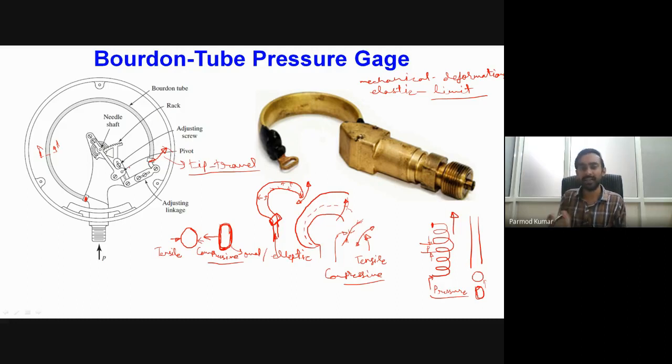So because of that, there will be development of some inaccuracies. So after a fixed duration, these types of gauges are recalibrated, and while they are recalibrated, over this mechanism we have an adjustment screw in order to adjust the scale of the gauge with reference to the corresponding material condition of the gauge at that particular instant.